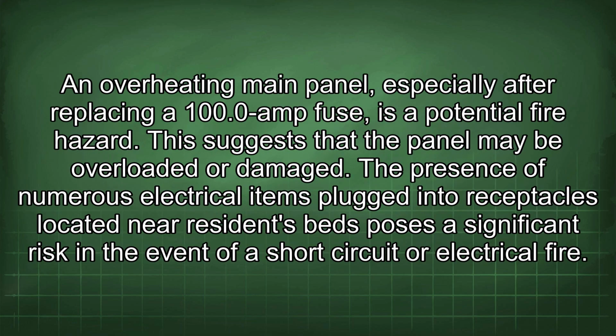An overheating main panel, especially after replacing a 100.0 amp fuse, is a potential fire hazard. This suggests that the panel may be overloaded or damaged. The presence of numerous electrical items plugged into receptacles located near resident's beds poses a significant risk in the event of a short circuit or electrical fire.